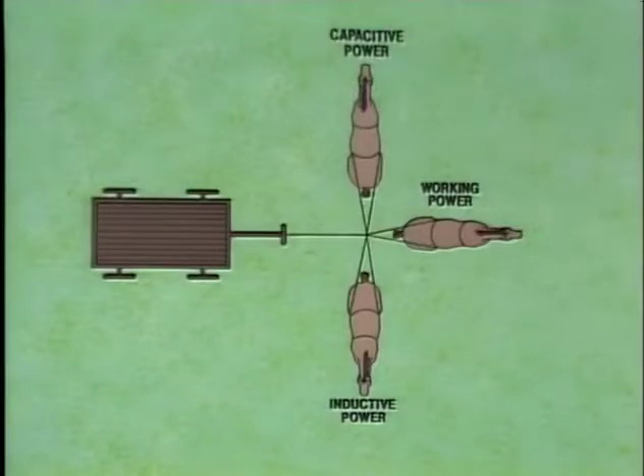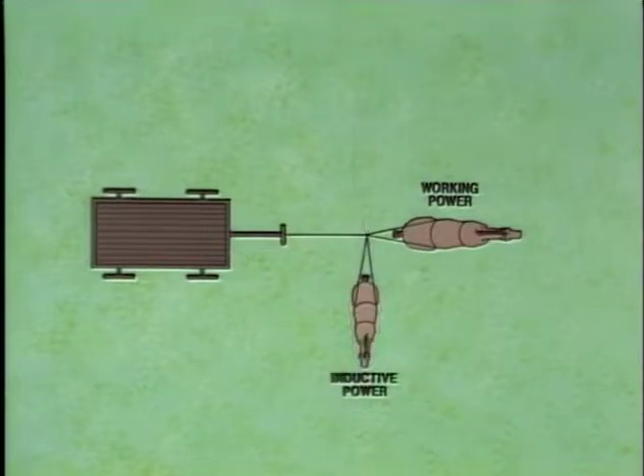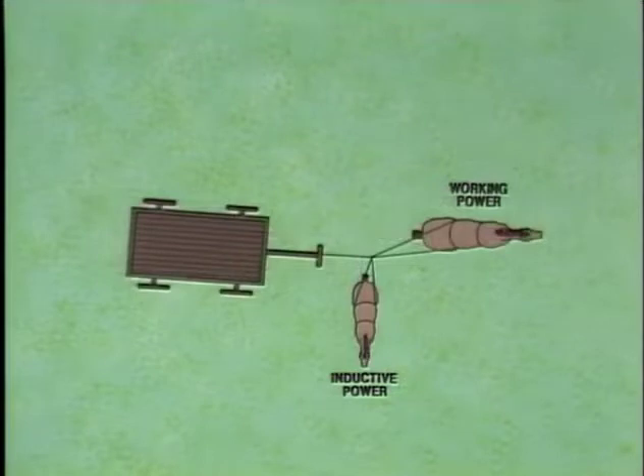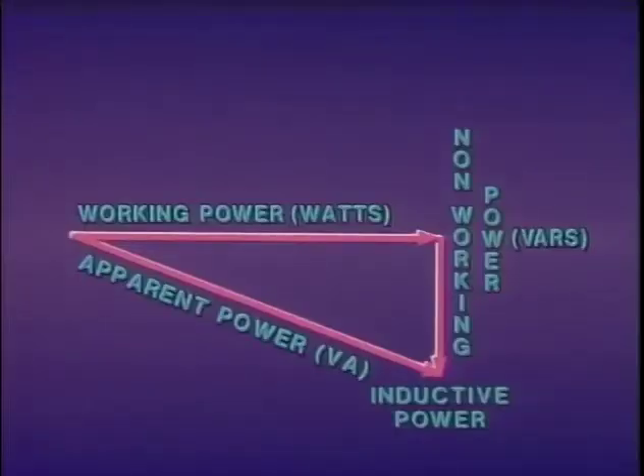Now suppose there is less capacitive power in the system than inductive power. The capacitive power will only cancel an equal part of the inductive power. The remaining inductive power, together with the working power, will move the wagon to the right and down. Work is being performed, but not as efficiently as when the capacitive and inductive power are completely canceled out. The power that a utility has to produce to meet the demands for both working power and non-working power is called apparent power.